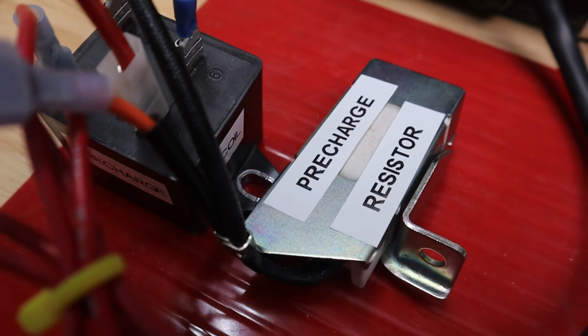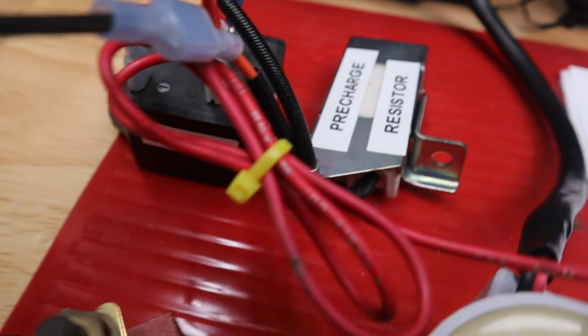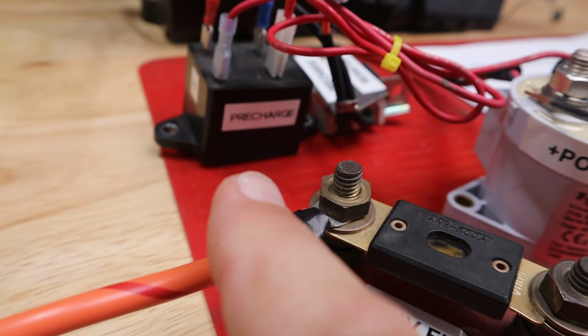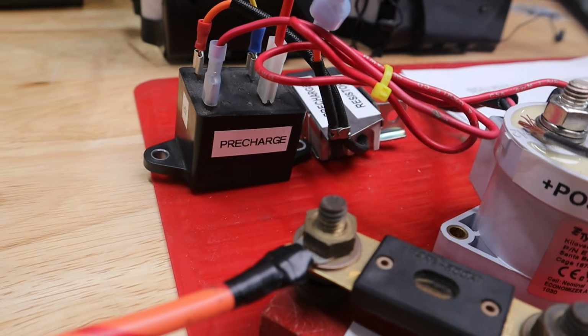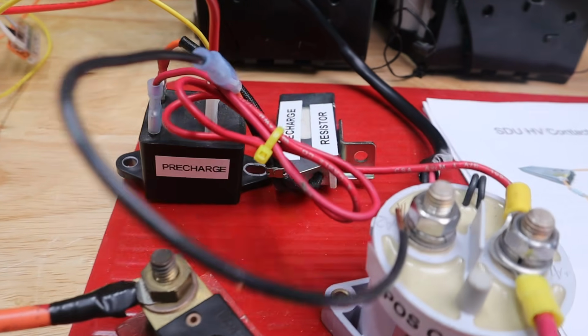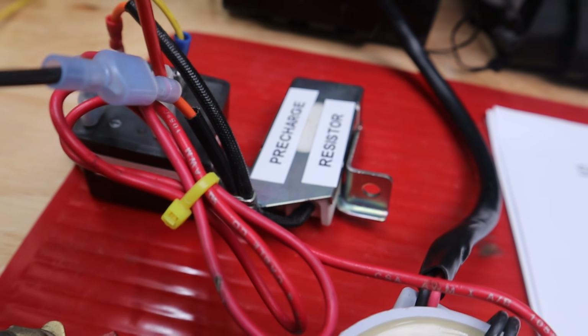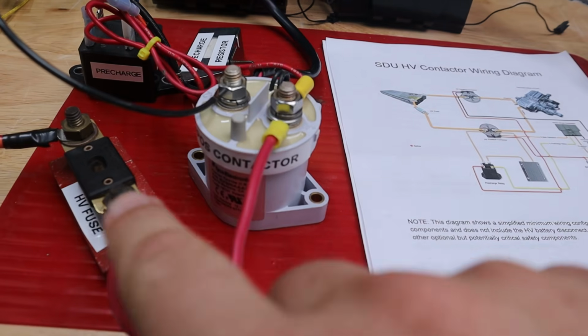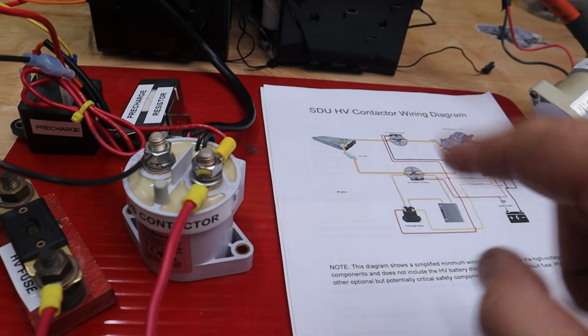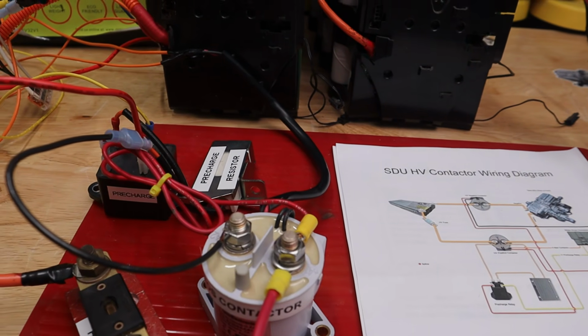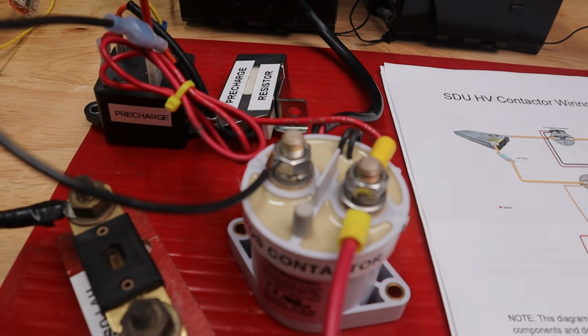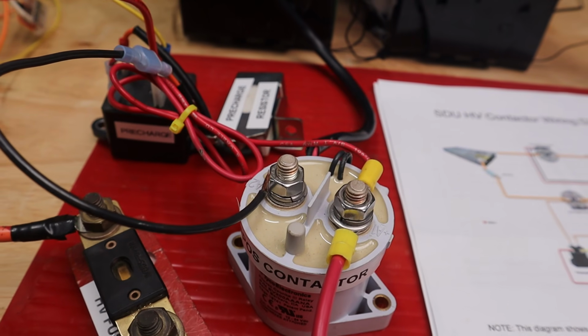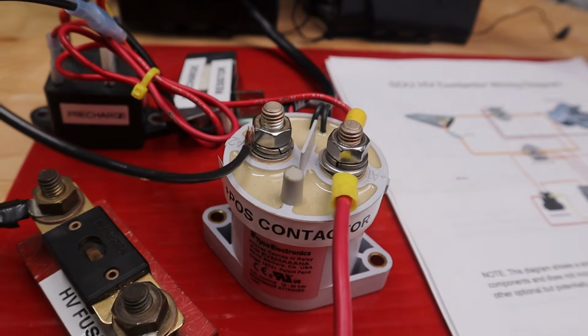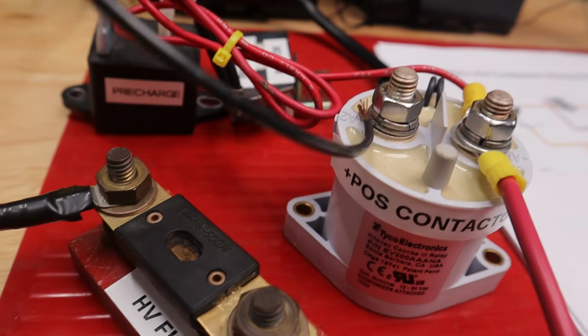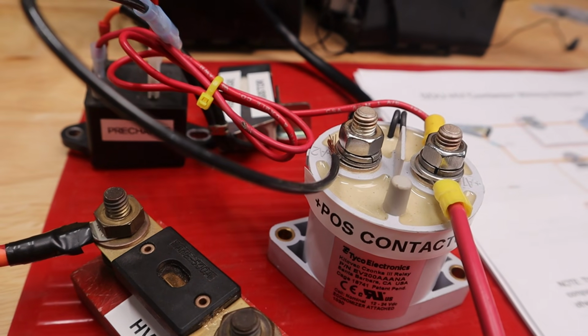So when you turn the system on, the Open Inverter board is going to turn on that pre-charge relay, which routes power through the pre-charge resistor, basically bypassing the contactor, then goes to the inverter and back to complete the circuit. It does that so there's not a sudden inrush current, which could damage capacitors in the inverter. So the contactor and pre-charge relay are both controlled by the Open Inverter board.